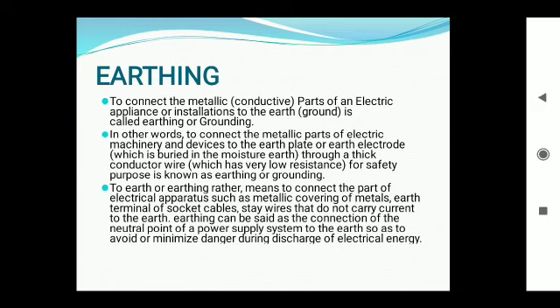the equipment earthing. When the earth wire is connected to the metallic plate or metallic cover of the electrical device, the cover which is not normally conducting the electric current, that means to protect the outer covers and to protect the operator from shock, you have to use the equipment earthing.